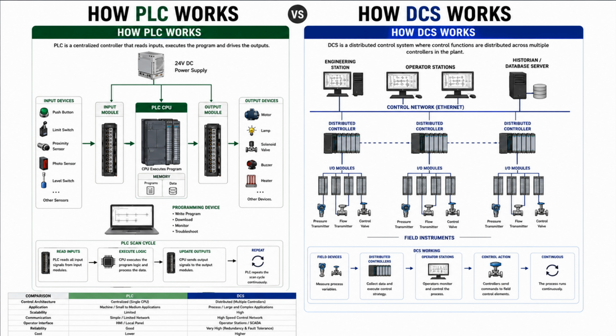So remember these three ideas. PLC controls machines. DCS controls entire processes. And both systems use the same basic principle. Read the inputs. Process the logic. Update the outputs. The difference is not in the purpose. The difference is in the scale. Once you understand that, choosing between PLC and DCS becomes much easier.